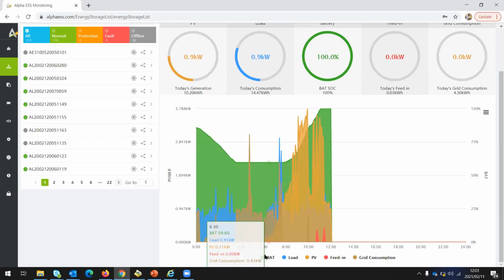The green is for battery. So it means this system at night was supplying the loads with battery up until around 3:40, when it reached the reserve SOC set, which I think is 60%, because the battery was around 59.6. Since the installer set this percentage to reserve the battery for load shedding, at that instance, grid took over and started supplying the loads. The battery stayed at 59 until 6 in the morning. From 3 to 6, the grid matched the load.